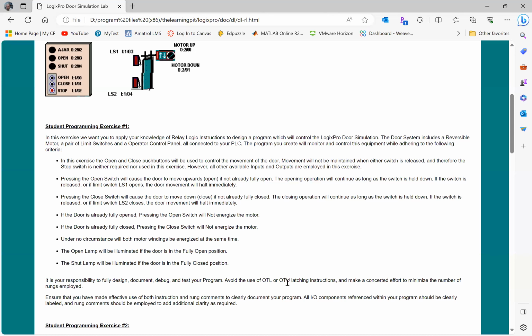They're going to have to use a latch function, an output that has a latch on it, and then somewhere down your program, you have to unlatch it at some point. That could be 500 rungs down. I don't know, but if they're both engaged or both off, it will not operate. And that is so hard to find.